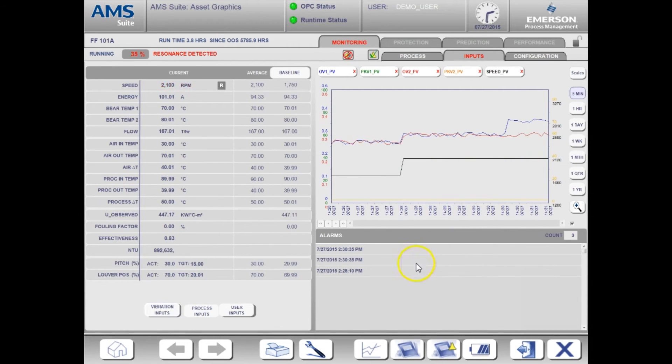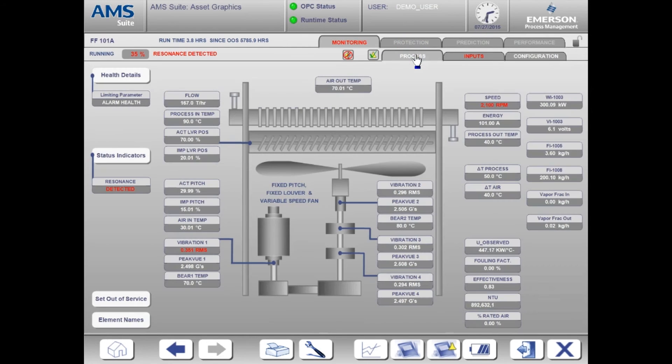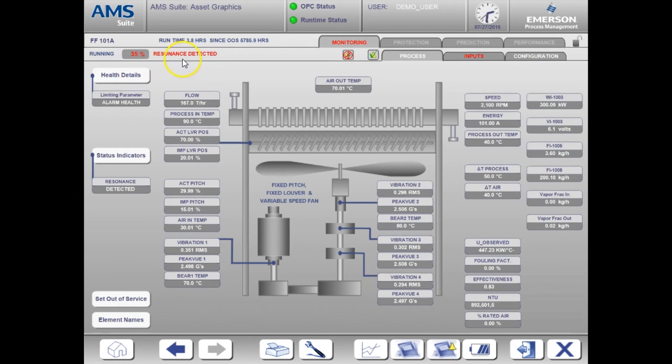Let's now go back to the process page. We can clearly see the critical health and the resonance alert active at the top left. We also have an indication of high vibration with the flashing red text.